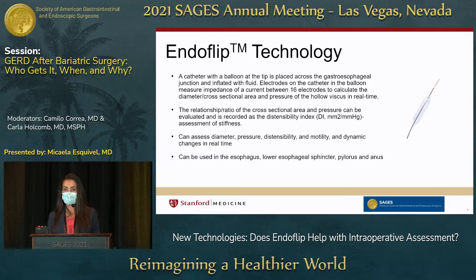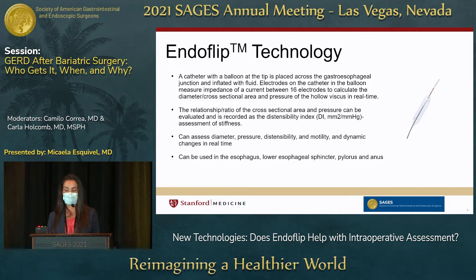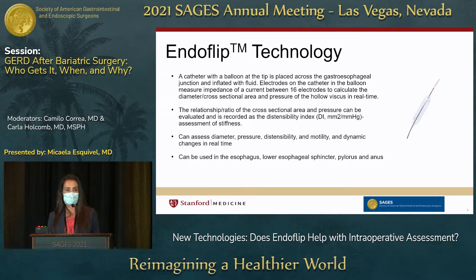The relationship — or the ratio of the cross-sectional area and pressure — can be evaluated and calculated as the distensibility index, an assessment of stiffness or compliance. With Endoflip, we can assess diameter, pressure, distensibility, and motility, and really look at dynamic changes of all of these in real time. It can be used in the esophagus, the lower esophageal sphincter, the pylorus, the anus, and more.